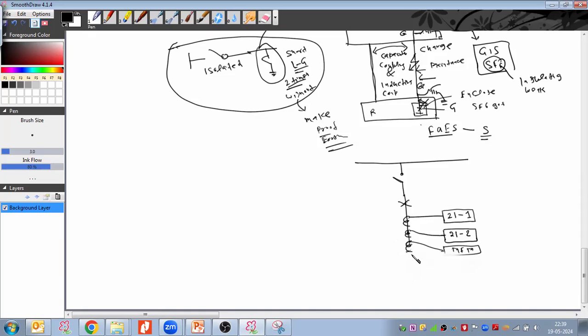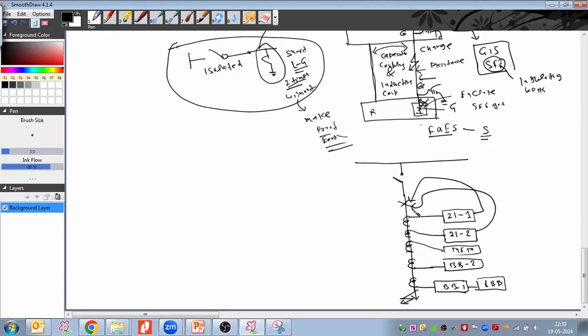So the CT here has the third core, then the fourth core and fifth core. This CT is looking towards the bus bar side. So bus bar 1 plus LBB, and bus bar 2 here, and the LBB also, local breaker backup. Now it is an outgoing feeder. What will happen when a fault occurs? First of all, the distance protection is going to trip the breaker, giving a tripping command to both trip coils of the circuit breaker, right? Suppose my breaker is mechanically stuck and fails to operate.